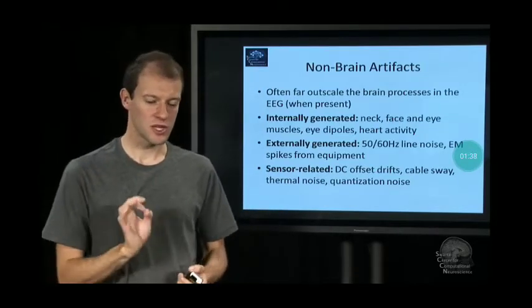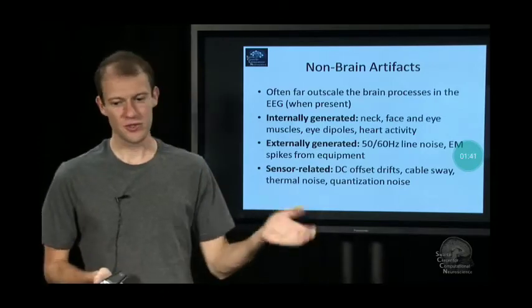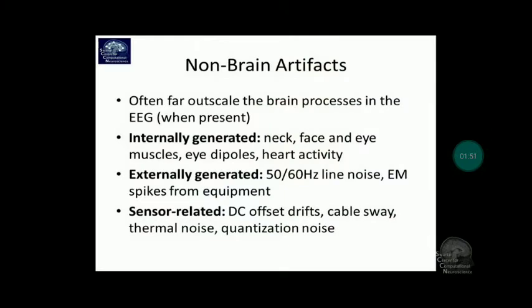And then there's some sensor artifacts. There's shifts in the signal amplitude called DC shifts or drifts, current basically. There's cable sway artifacts. If your cables are swaying around, you get lots of low-frequency shifts. There's thermal noise of the interface between the metal of the electrode and the skin.